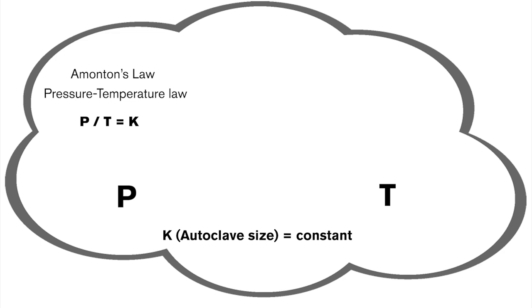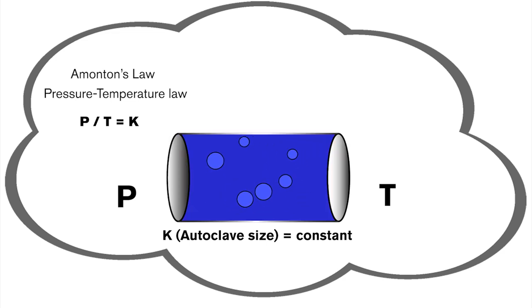For example, when you boil water in a sealed container, like a pressure cooker, where the container size is constant, therefore keeping the volume constant, the temperature rises, which also leads to increased pressure inside the container. What you may be thinking is that an autoclave is also a robust and well-engineered pressure cooker, and you are correct.